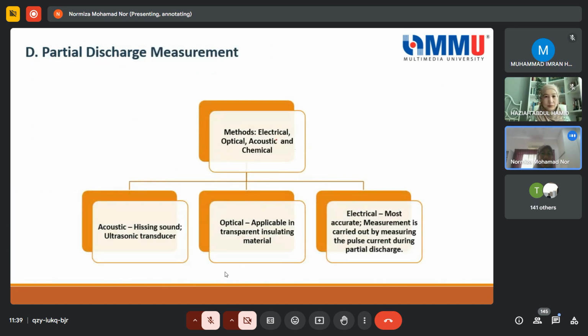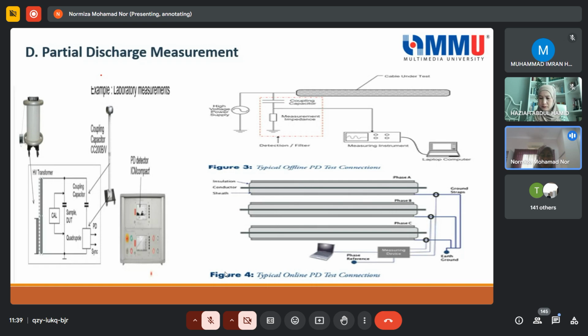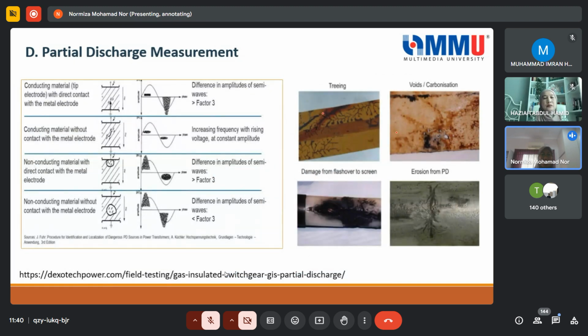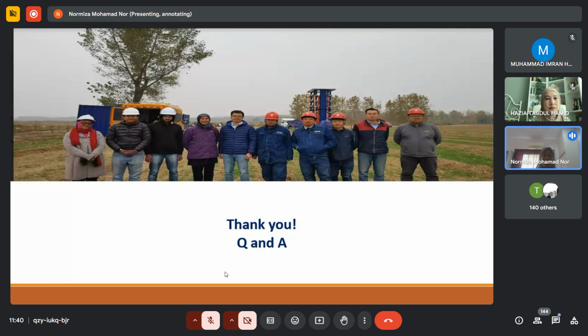So there are a few methods: electrical, acoustic, optical. The electrical is the common one. As I mentioned before, I will just go very briefly. This is for laboratory measurement, and this is the typical offline, and this is online, which can be remotely monitored. The partial discharge actually has voids, and once we run the test, we'll be able to diagnose whether it is due to different types of partial discharge, such as cavity, corona, treeing, and surface discharge.